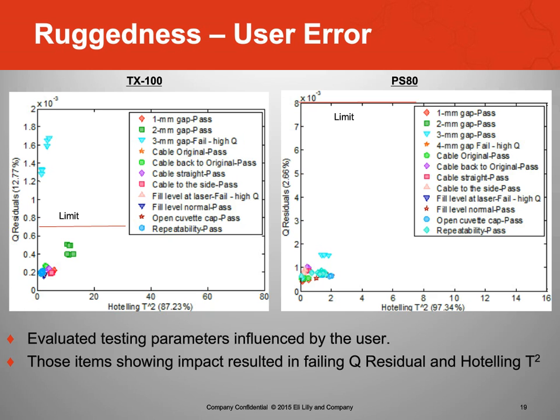We also looked at fill level. What if the analyst forgot to fill it completely? Well, to catch it, in this case the fill level is right at laser, right where the laser hits. It failed. So we just know it wasn't full. And it doesn't matter if it has a lid on it. And then the control here is repeatability. We looked at multiple runs of the same thing at method conditions, and obviously it passed. So for all practical purposes, ruggedness can be designed into the method, and we can capture when it's being run accurately and consistently.